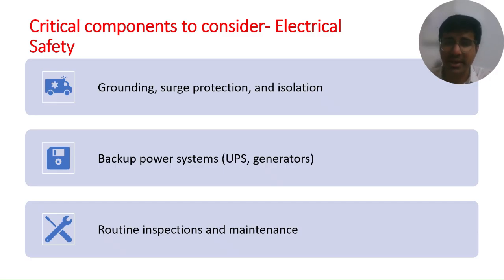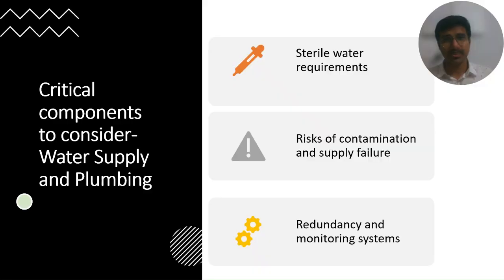A voltage spike can fry life-saving equipment like your ventilator. Backup systems should be checked - your UPS, generators, etc. So when was the last time your OT's UPS was load tested, or your isolation transformer, if you have one, calibrated? Are routine inspections happening? Is the maintenance being recorded on an audit sheet or paper? Is it well recorded? These are things you must consider and think about.